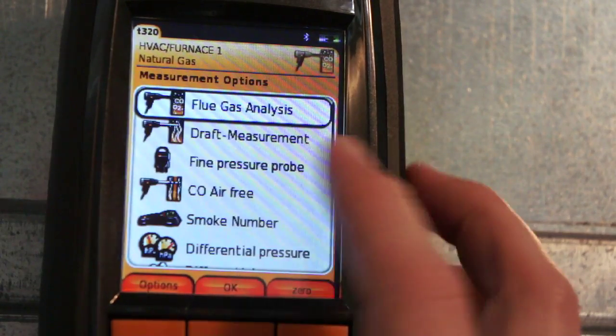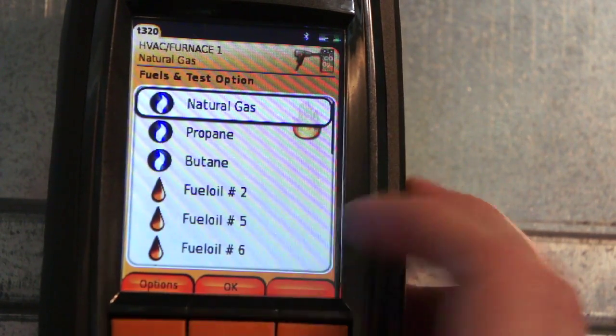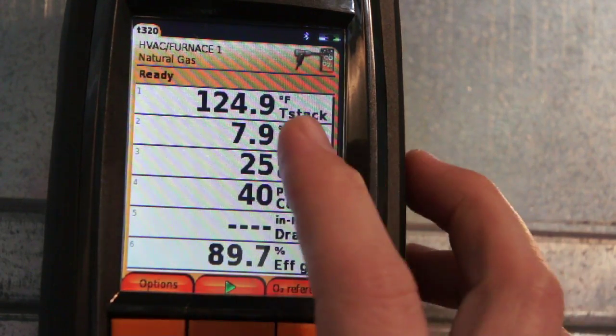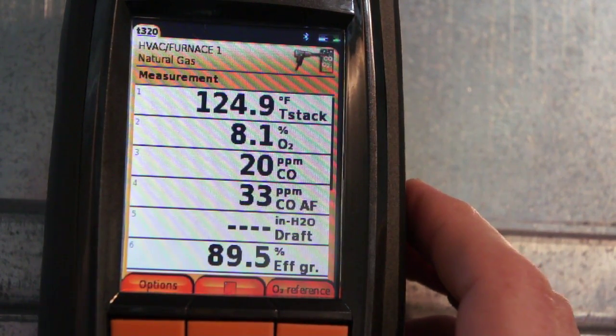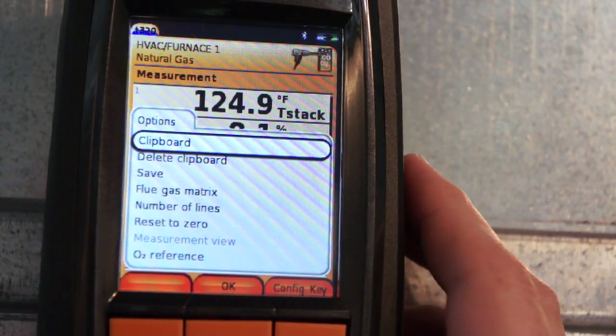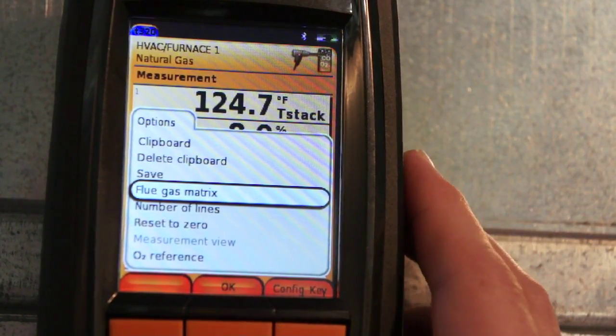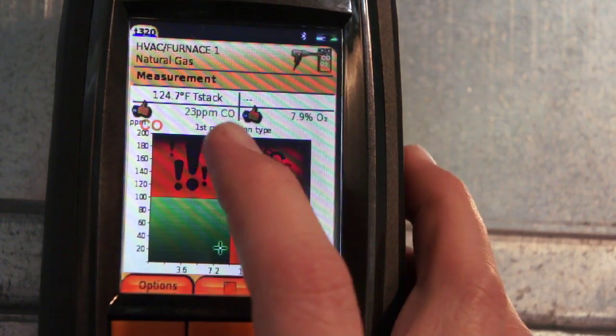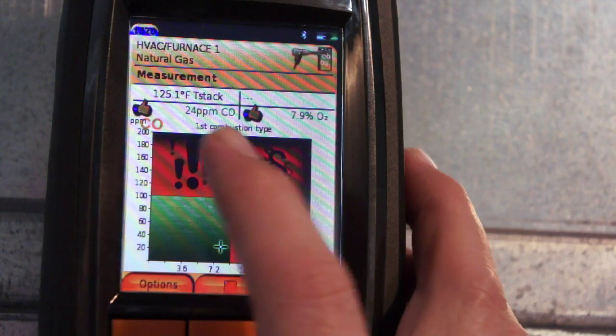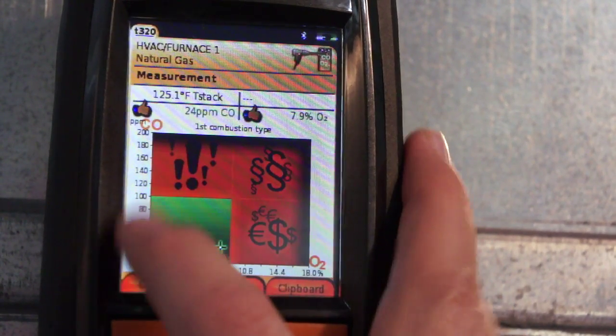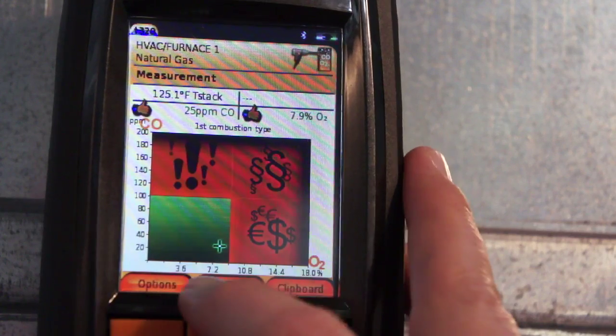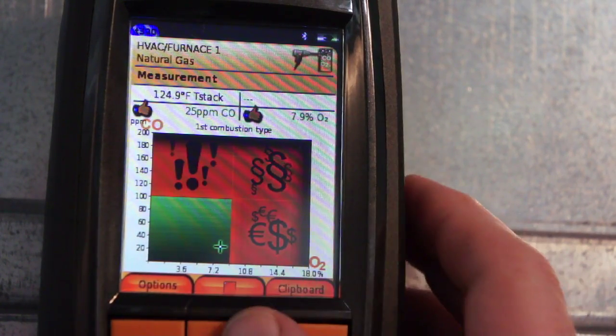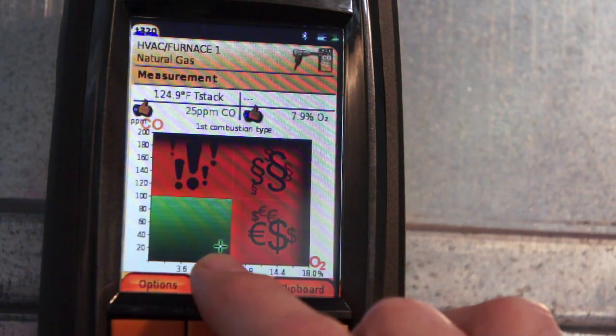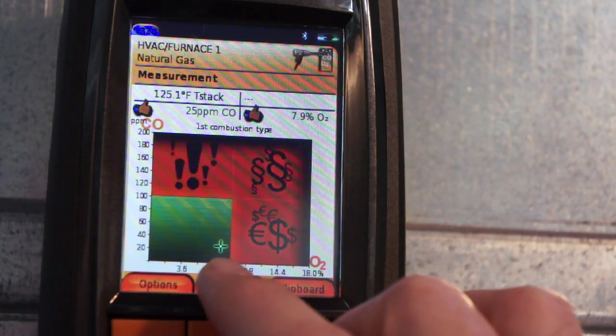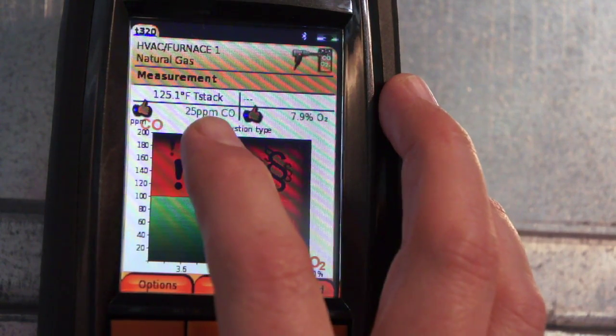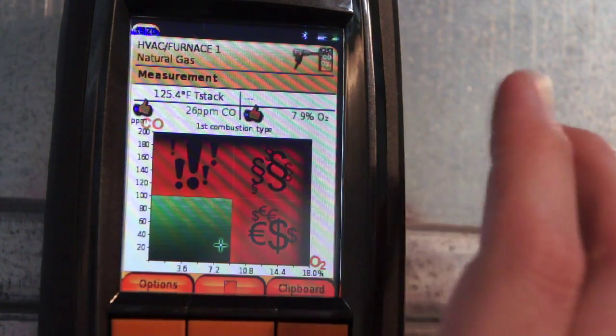Now I'm going to go back into testing, natural gas OK, and flue gas OK, and now I'm back in and I'm going to start my combustion test again, and you know, nothing's changed here, but I'm going to go into options and I'm going to go into my flue gas matrix now. When I go into the flue gas matrix, you can see that it says it's optimized for my CO. It goes 0 to 200 here, right? So the top end of the range is 200. My O2, my top of the range is 9%. I'm in the green zone here, which indicates that I'm in the combustion zone I want to be in. I have good combustion. I have thumbs up on both. CO is 25, O2 is 7.9%, so I'm in the safe zone.